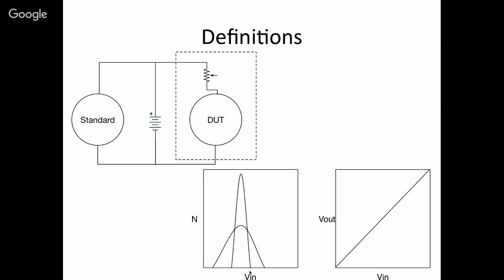So this is just a comparison of populations of measurements given some input voltage and the number that you're actually getting. So if you take 1 million measurements on the standard and 1 million measurements on the DUT, or even if you take 10 on each, you're going to see this sort of curve develop on the higher uncertainty, lower precision device, the cheaper one usually, and this sort of curve develop on the higher precision device.